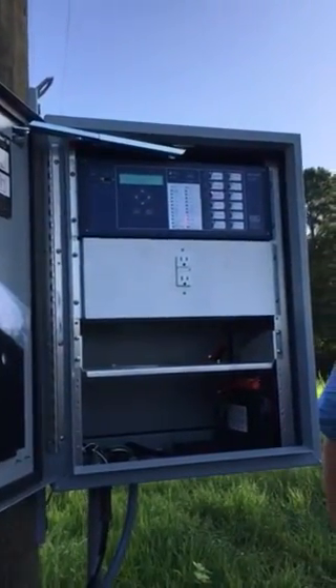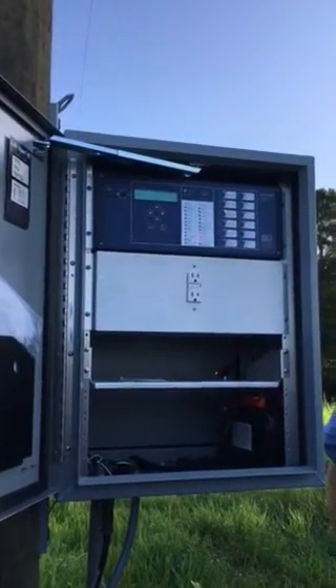So right now, the lineman does not have to get a one shot. The only time that we would come here is to get an open point, as far as if one of these poles broke in this area, and then you'd have to come and open up your PKRs to get your air gap. However your procedure is for that, you'd have to do that. But it's permanently on one shot. So once something comes through or you trip, it's coming offline, it's locking out and staying out. It's not closing back. It doesn't have any reclose at all in it.